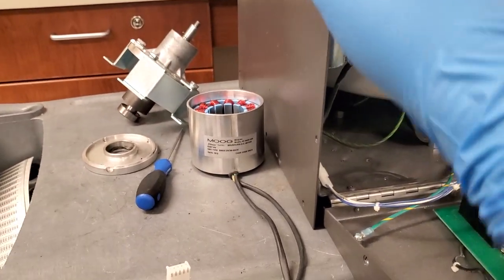These ones here are way more durable. The speed control, which is actually done right under here - the driver - is so much more efficient than brush motors. Brush motors also will generate EMF, which is electrical noise. If you have a small centrifuge like this in a laboratory near a certain device, or in an operating room, which they do have small centrifuges in, then that EMF is going to interfere with other devices like EEG.